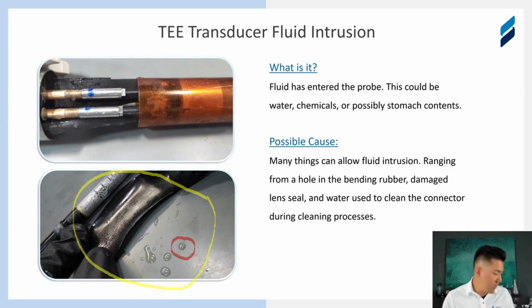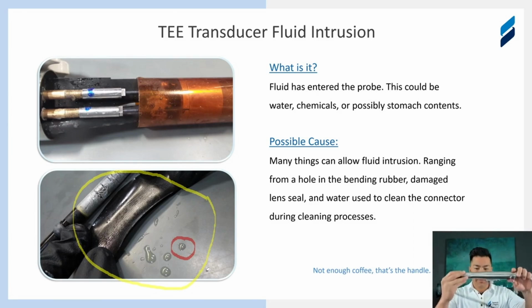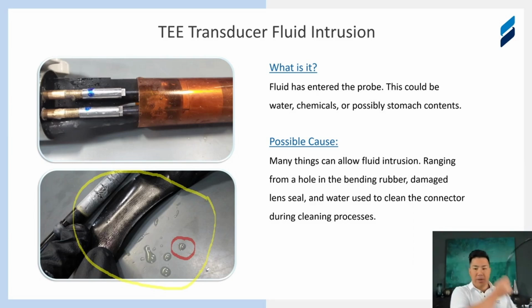And same thing here. This is the connector of a TEE probe, and the connector would be this portion with the controls. The fluid would get in on the tip or the bending rubber, and it would actually slide all the way down and drip into the handle. Or the handle wasn't properly sealed and it accidentally got dunked in some water or whatever fluid is being used to clean these probes. But as you can see on the top picture here, there's just a lot of fluid in there, and fluid and electronics just don't mix. So here are some examples of what we see on the other side if you identify some punctures and potential fluid ingress.